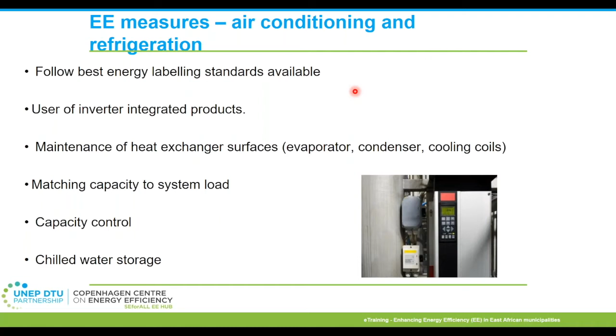This is one of the case studies from a building. I'll directly jump into the result. This line represents the specific power consumption for chiller 1, which was integrated with a variable frequency drive, and this one represents the specific power consumption for chiller 2, which does not have a variable frequency drive. You should note that both the chillers are of the same capacity and were subjected to the same conditions.